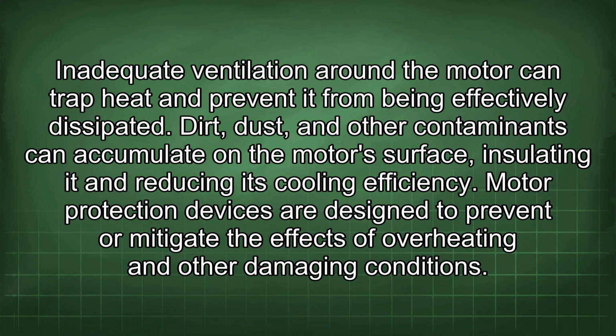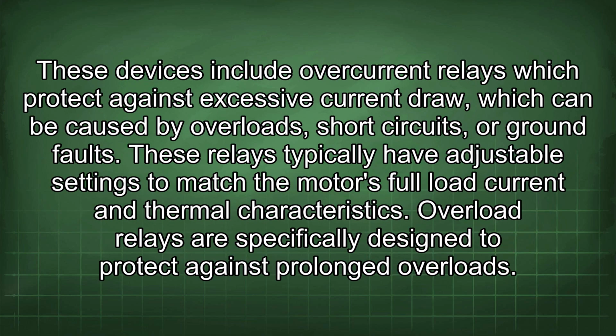Motor protection devices are designed to prevent or mitigate the effects of overheating and other damaging conditions. These devices include overcurrent relays which protect against excessive current draw, which can be caused by overloads, short circuits, or ground faults. These relays typically have adjustable settings to match the motor's full load current and thermal characteristics. Overload relays are specifically designed to protect against prolonged overloads.